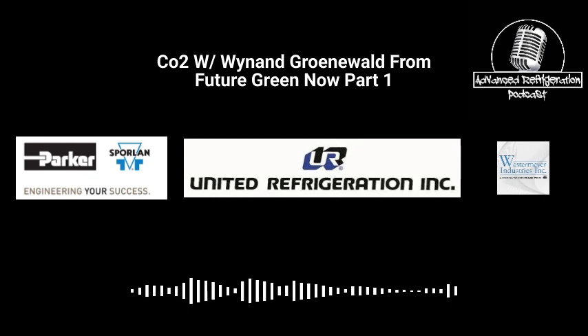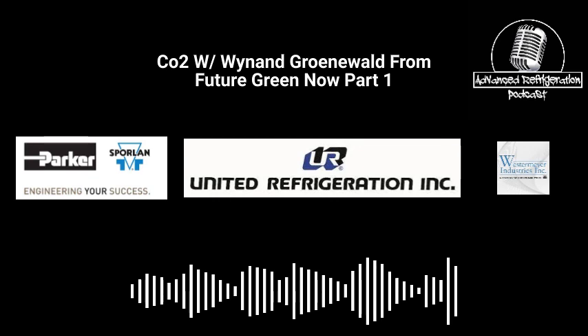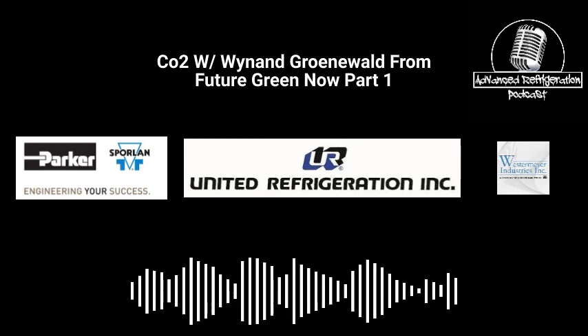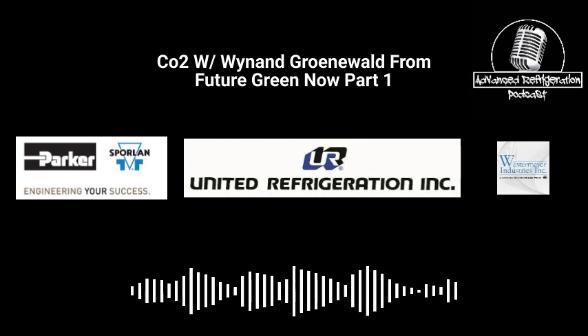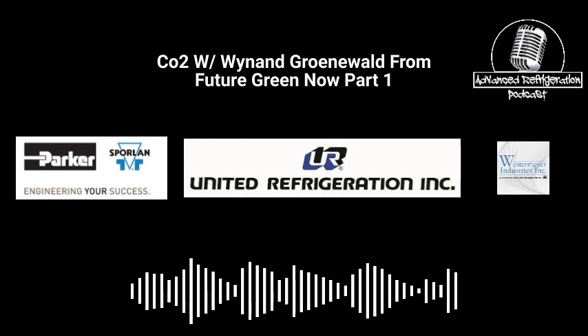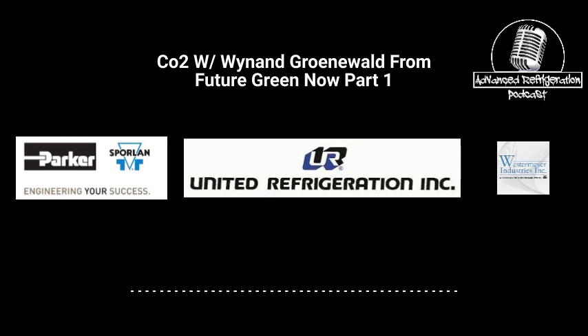Is there any downside to having that do that? Because I've seen some of the older racks used to be set for only 3 degrees. Now they seem to be doing 5 degrees, and I've seen some customers say, yeah, we're going to jack it up to 10 degrees of subcool, but then it clamps down on the HPV too much. So by changing that subcooling set point, is there any kind of bad thing that might happen by doing that?